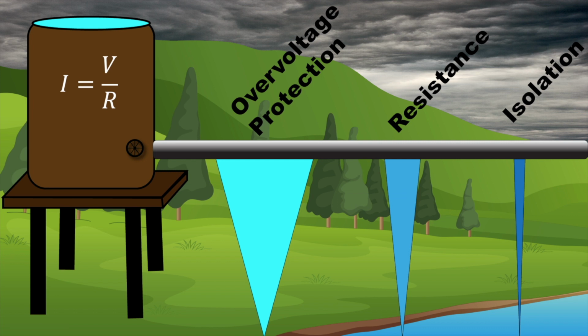So you've got the first level as over voltage protection, then resistance, then isolation. With all of that together, we're able to maintain that IEC 61010 rating.